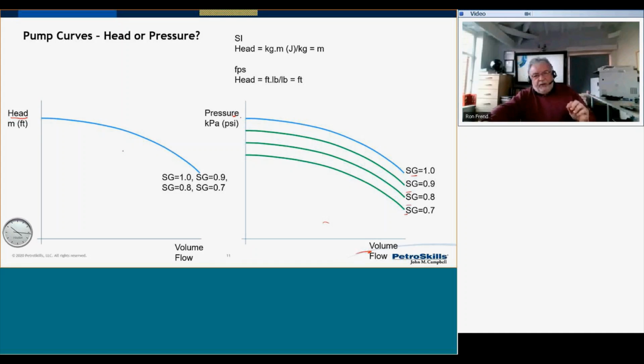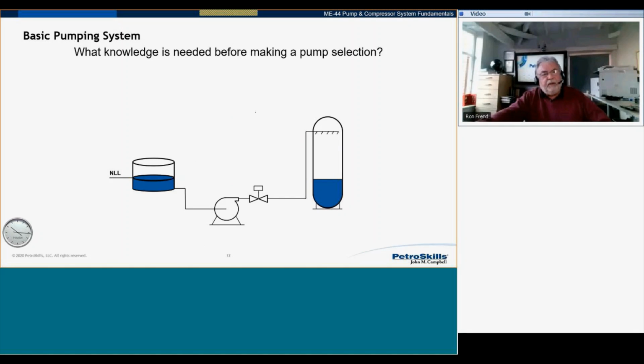So the reason for going through all this is that I am going to develop a system curve. And by developing the system curve, I've got to figure out what are the best units to do this in. We're going to use head. Okay. So we've got a fairly basic system. We're going to go from a storage tank through a pump, and we're going to pump up to another tank. It's going to be a pressurized vessel. And the first thing we've got to think about is what information I need to be able to help me select this pump.